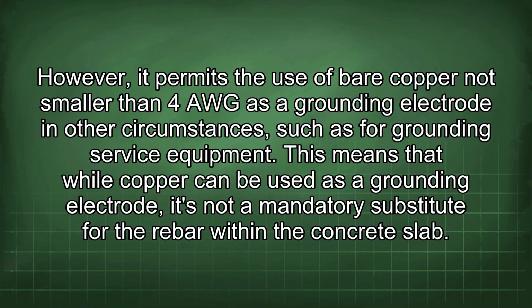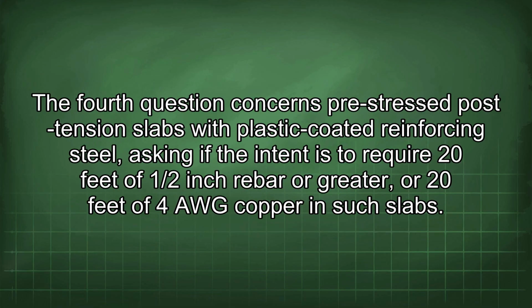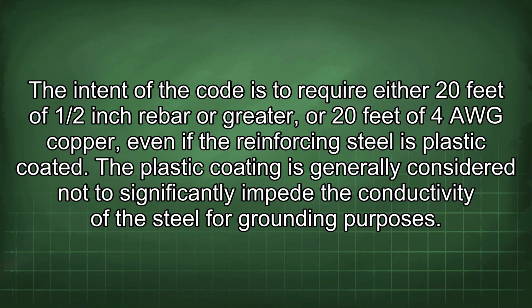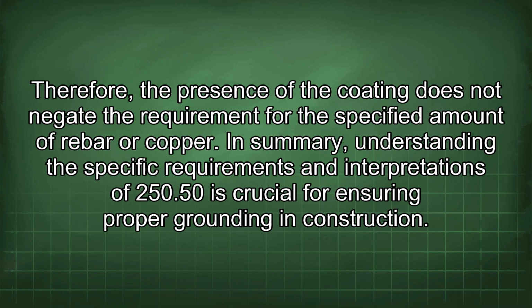within the concrete slab. The fourth question concerns pre-stressed post-tension slabs with plastic-coated reinforcing steel, asking if the intent is to require 20 feet of 1/2 inch rebar or greater, or 20 feet of 4 AWG copper in such slabs. The intent of the code is to require either 20 feet of 1/2 inch rebar or greater, or 20 feet of 4 AWG copper, even if the reinforcing steel is plastic coated. The plastic coating is generally considered not to significantly impede the conductivity of the steel for grounding purposes. Therefore, the presence of the coating does not negate the requirement for the specified amount of rebar or copper.